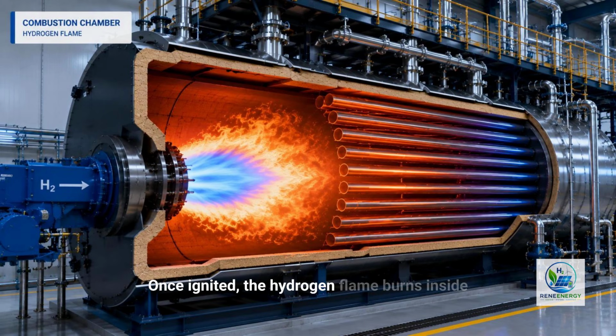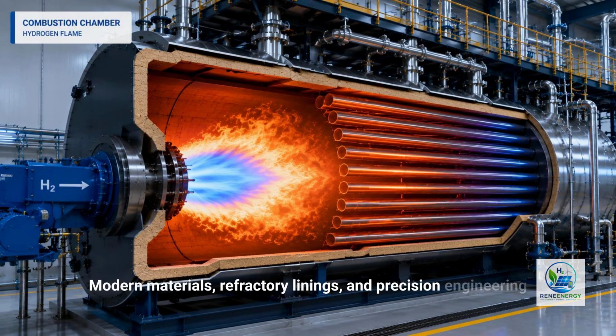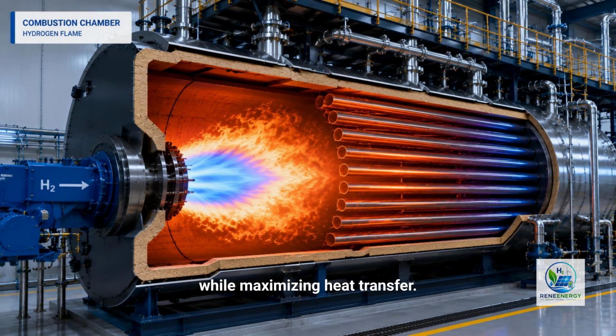Once ignited, the hydrogen flame burns inside the combustion chamber. Temperatures quickly rise to well over 1,000 degrees Celsius, creating an intense environment where chemical energy is converted into thermal energy. The chamber must withstand these extreme temperatures while directing the hot combustion gases through carefully engineered pathways. Modern materials, refractory linings, and precision engineering protect the pressure vessel from thermal damage while maximizing heat transfer. This is the point where hydrogen's stored energy is fully released, beginning its transformation into useful industrial heat.